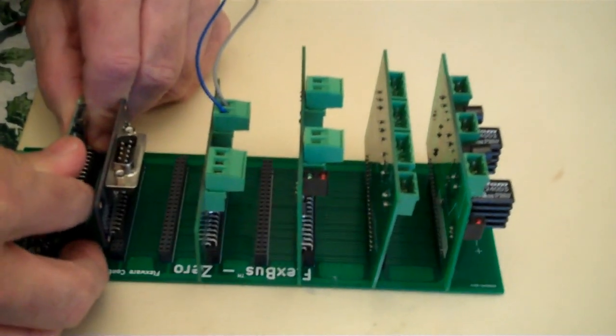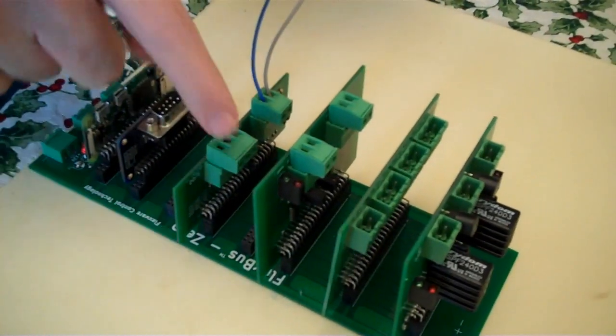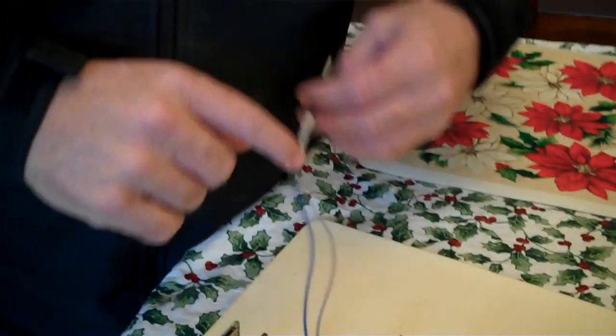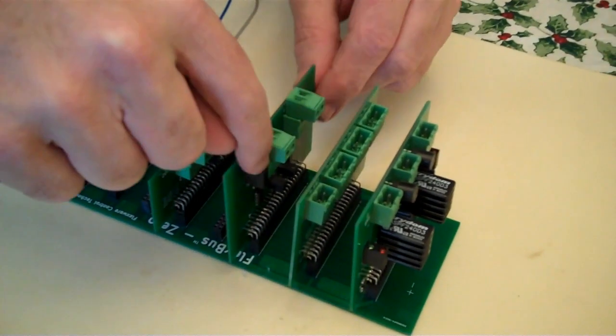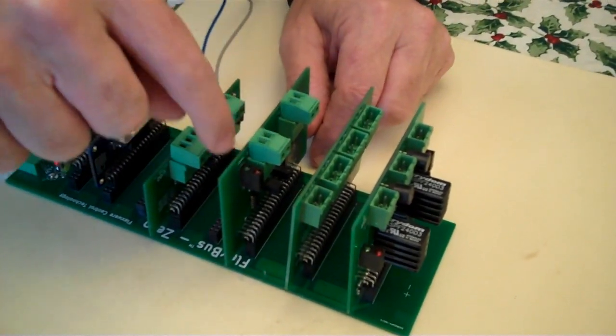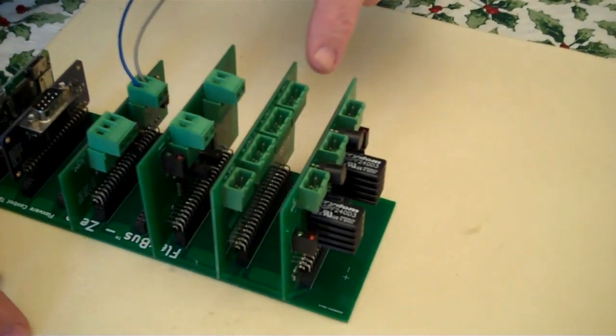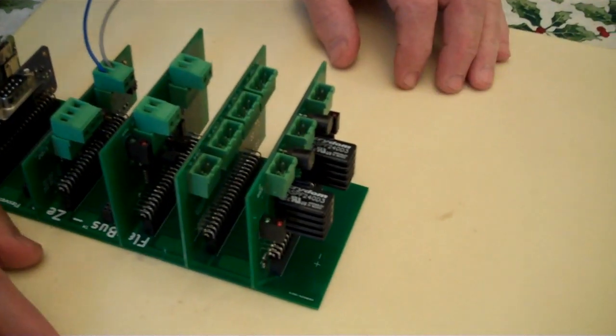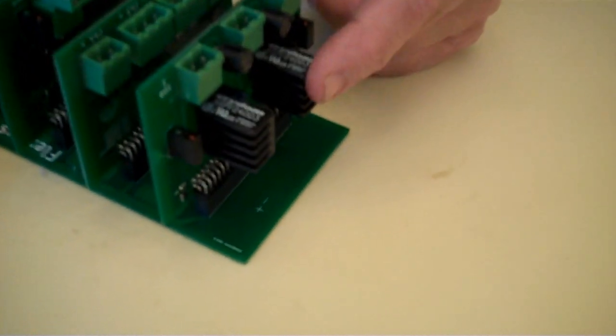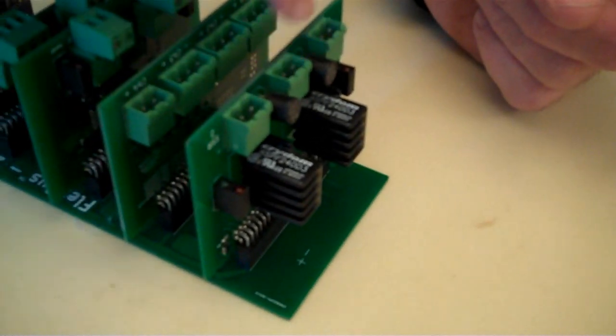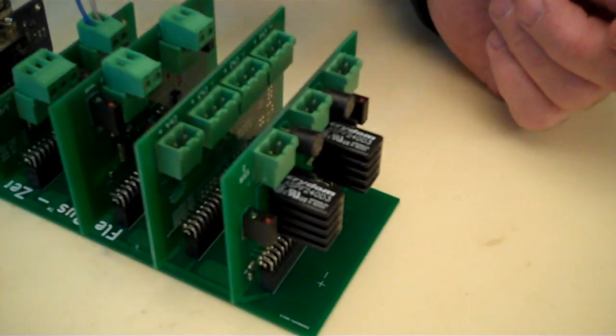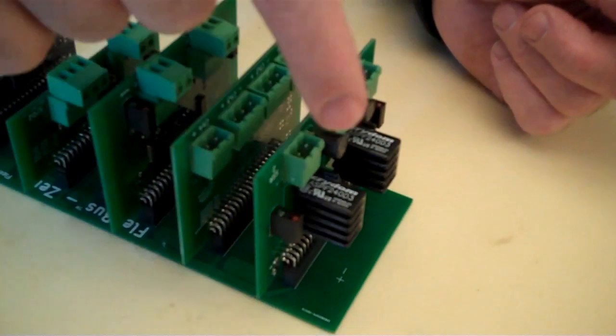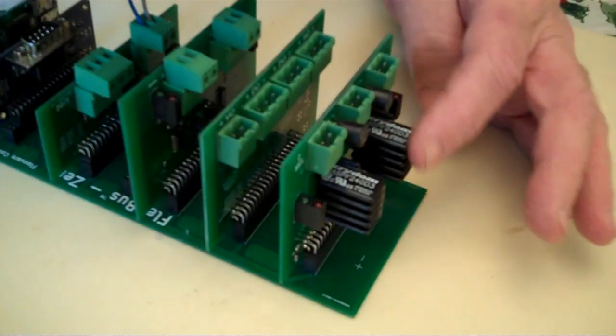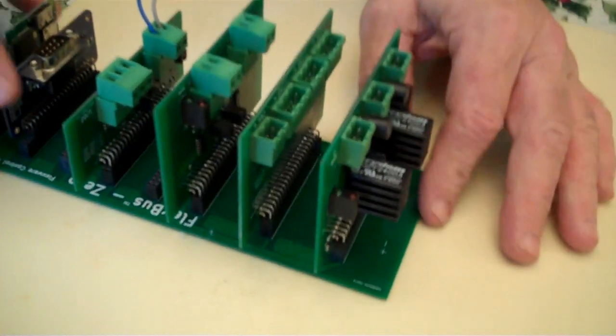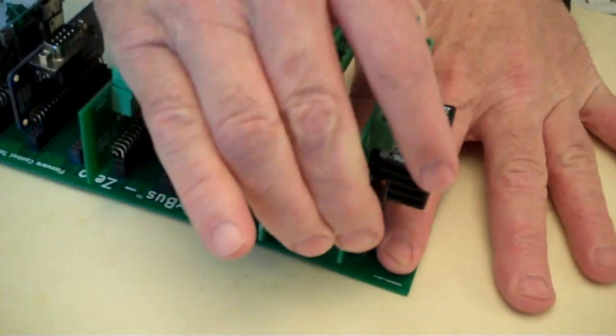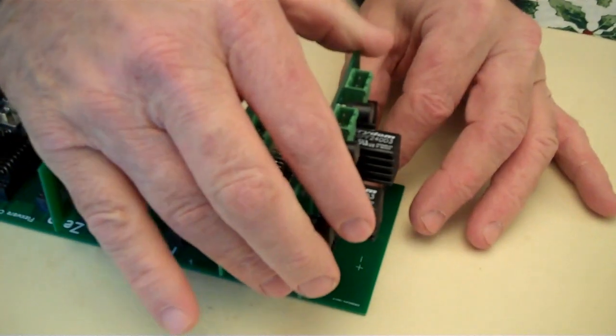The first card here runs RS-485. This card here is for the Dallas One Wire technology. This is two digital inputs, and they all have LEDs to tell you whether it's on or off. This is all analog that takes pressure transducers and thermistors. And then this is a solid-state relay board with two channel outputs. We bring the power in here, and we can have neutral and 110 volts feeding a solenoid or a contactor. That's the solid-state relay with heat sinks on them. And anytime you have a problem, you can always pull a board out and plug another board back in.